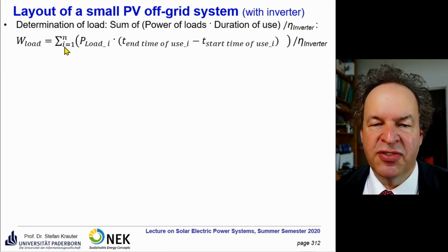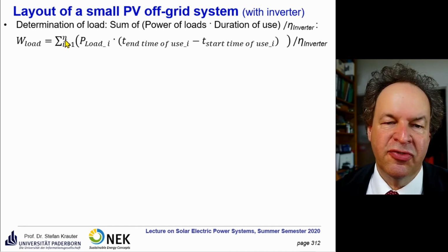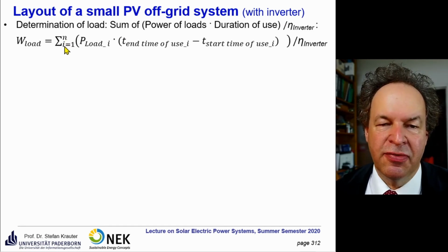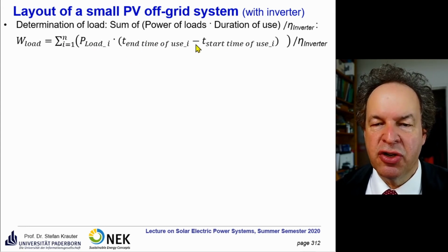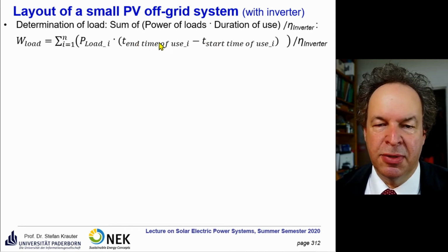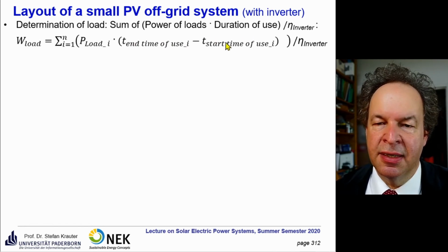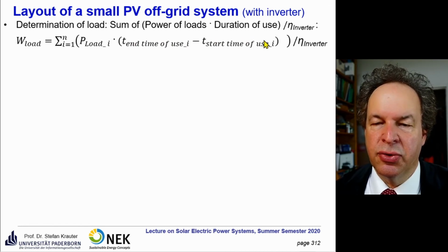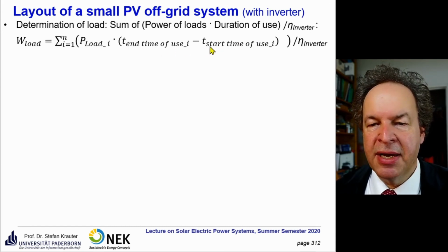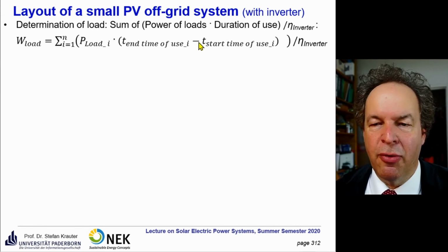But usually you have several loads. For example, here it's calculated for n loads. So you start with i equals 1, this is the first load. So it's the power, and then you have the duration of use. Usually you take the end of the time of use, for example here at midnight, and you start using it at 7 o'clock in the evening. So you have 24 minus 19, then you have 5 hours of use.